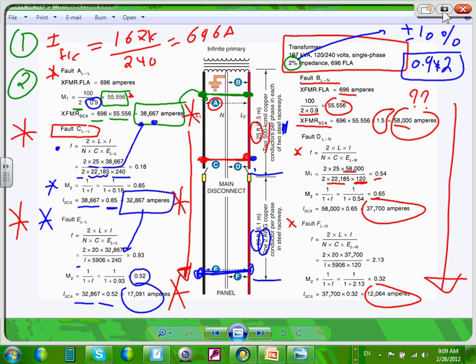Here's what you need to understand. We don't throw the panels, guys, based on the short circuit. We put the panel where we need to, and then we design the short circuit to match. But you have to understand when you do short circuit calculation, the panel close to the service transformer will have a very high short circuit compared to the panel that's further down the system.